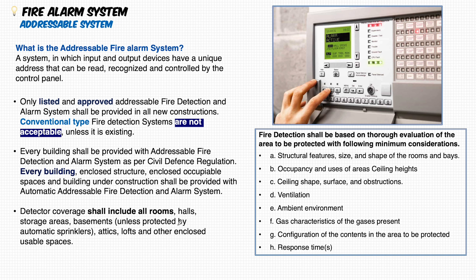The addressable fire alarm system — you've surely heard about it, as well as the conventional type. The addressable system is one in which input and output devices have a unique address that can be read, recognized, and controlled by the control panel. Each device has a unique ID address, so in case of fire, the panel knows exactly which device triggered.